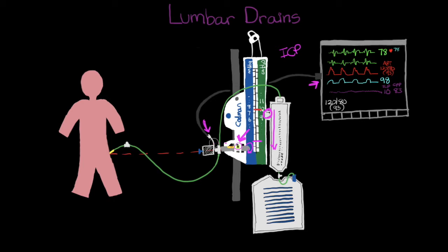Then what you're going to do is turn your panel stopcock off to the patient. This way you're running from your transducer up to the drain, and this is where we're going to get our quote-unquote open to air. We're never going to take the cap off the end of the transducer. We simply adjust the panel stopcock so that we're going from the transducer to the drip chamber. Again, remember, we want to minimize how much we're opening this system, so that's why we would not remove the stopcock on the end there.